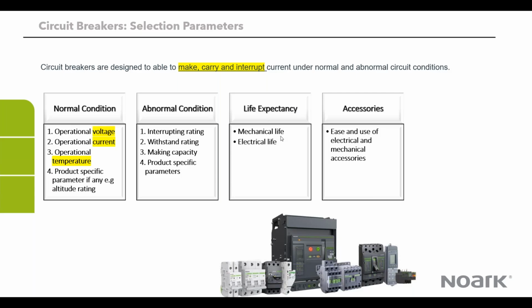The other thing you want to look out for when you are trying to select a circuit breaker is the life expectancy. The mechanical life is the life without the load connected, and then you have the electrical life, which is when you have the load connected. These values typically are not the same, so you need to watch out for that in the technical specification, because that determines the longevity of the circuit breaker. And then, of course, the other parameter to look out for is the accessories, because the circuit breaker should be able to do some remote control, some other kind of monitoring and measurement, and all kinds of accessories should be available for you to do those things. So you're going to have electrical accessories, mechanical accessories, all kinds of accessories. Typically, a circuit breaker should have the ability to adapt to the customer specific application.